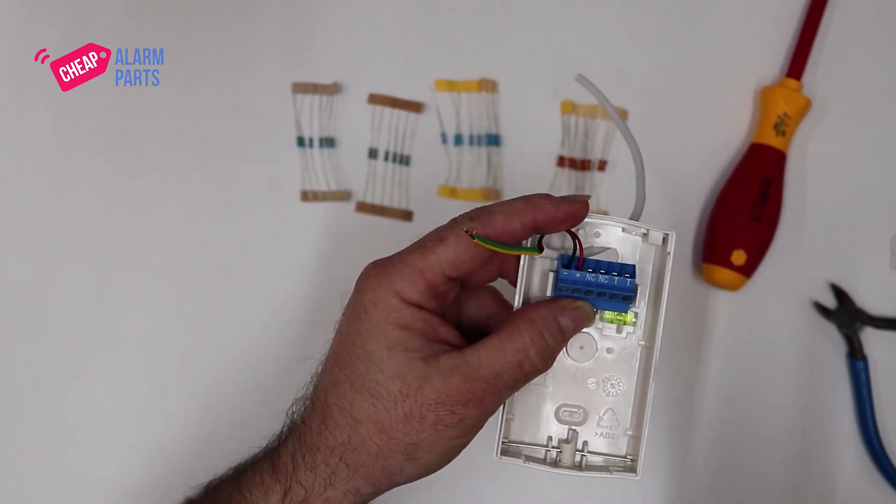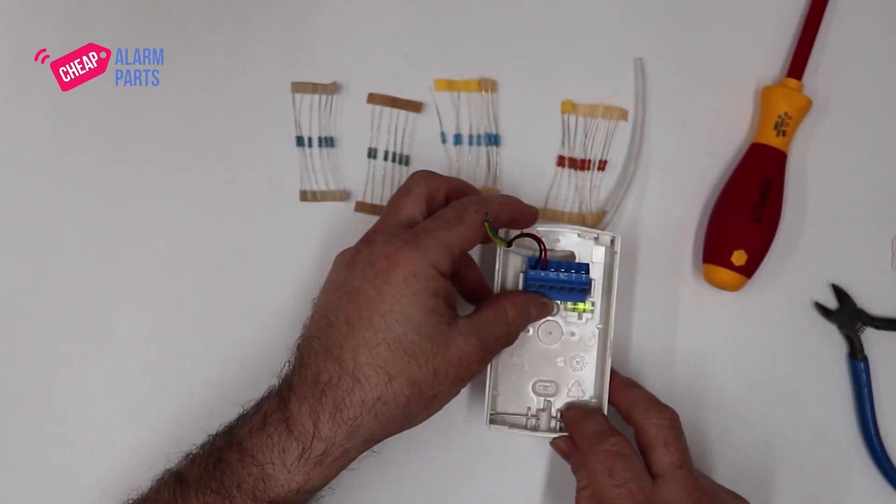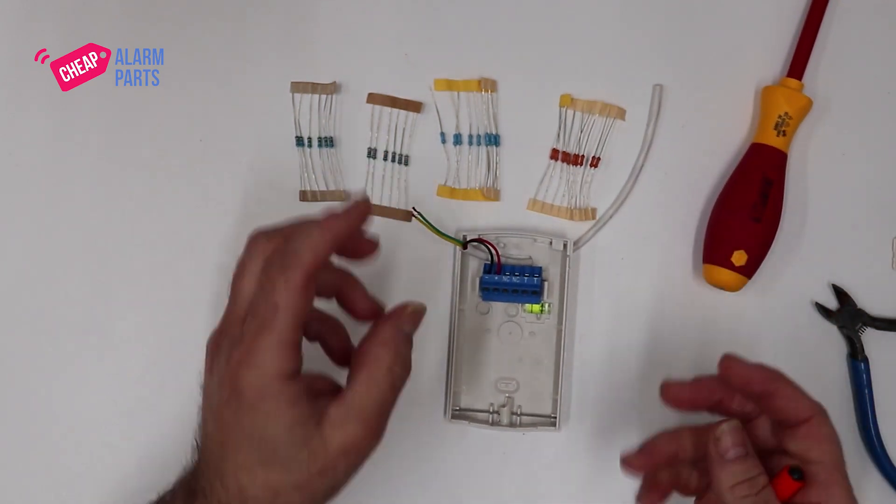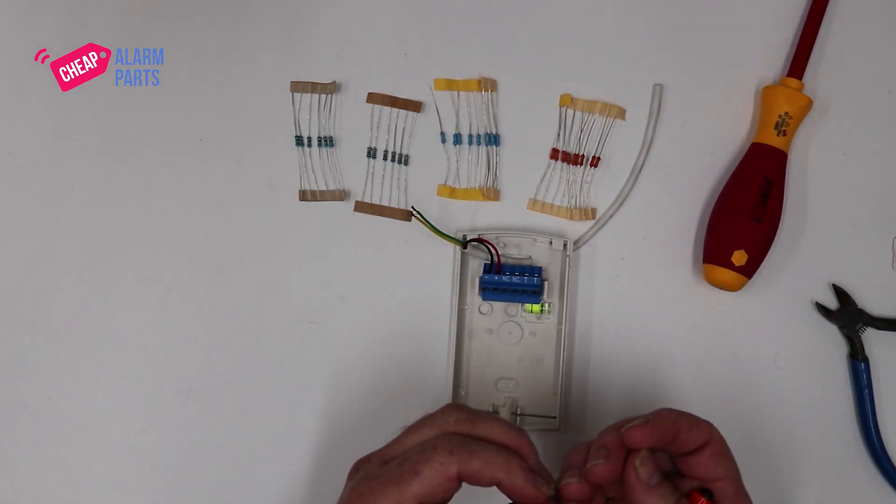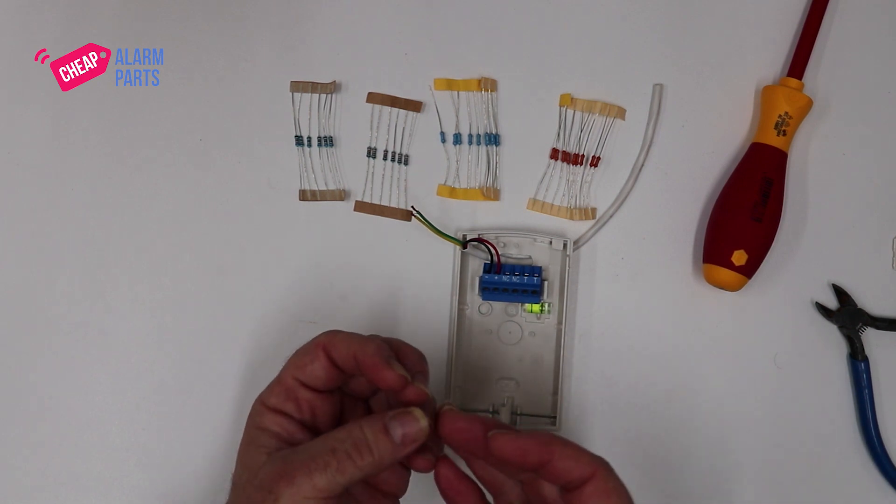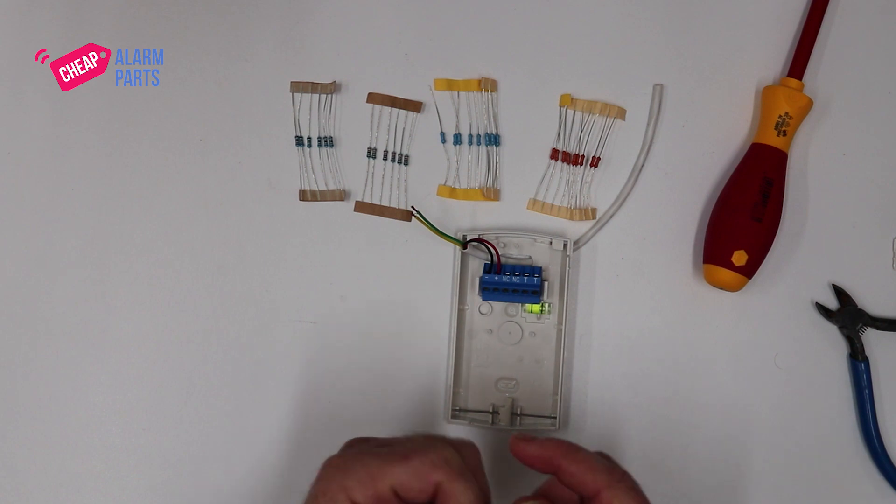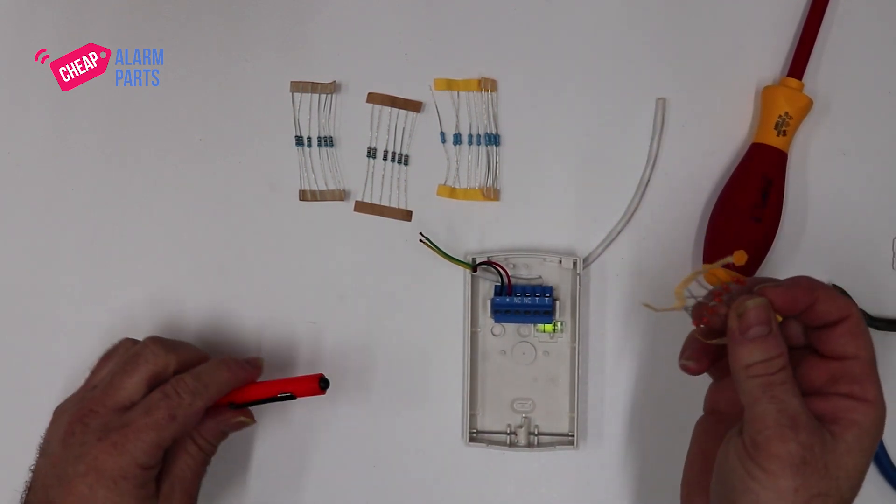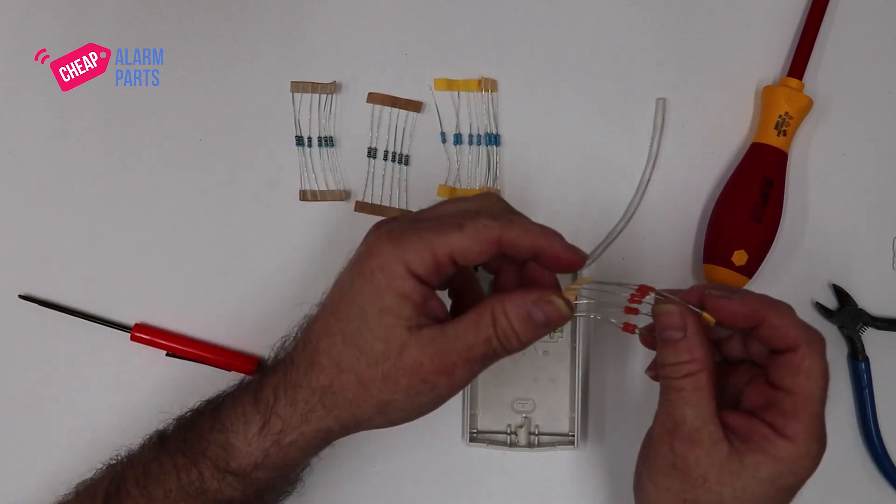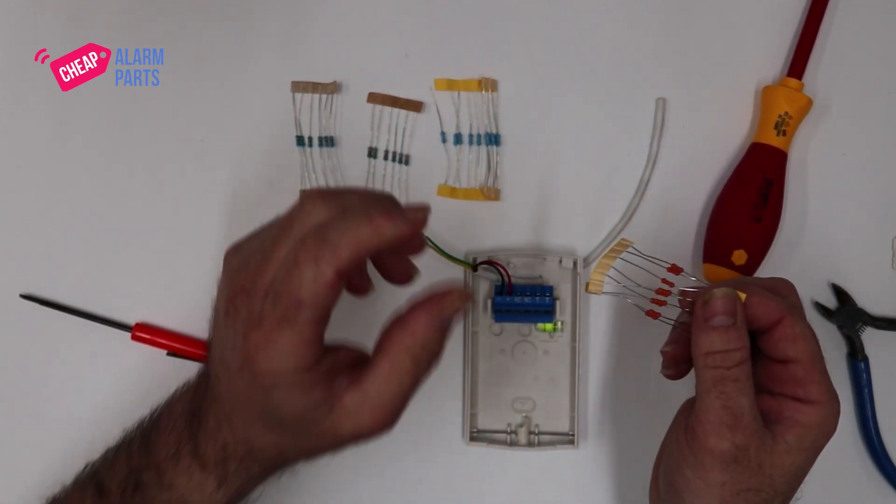Now, each sensor needs a resistor, and this is what the alarm panel is actually looking for. It protects your cabling. If someone shorts out your cabling, the resistance of the alarm circuit loop becomes zero. If someone cuts the cable, the resistance becomes infinite or open circuit. Only when the resistor is connected properly and not seeing movement does the alarm see the 3.3k or 6.8k resistance of the alarm loop.